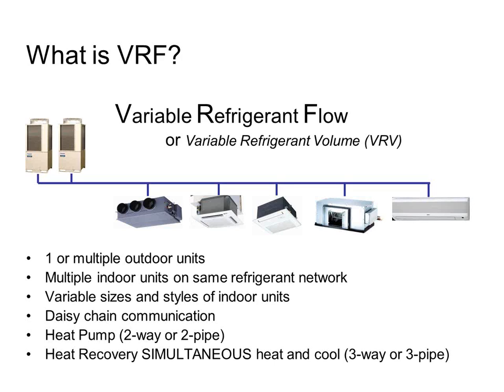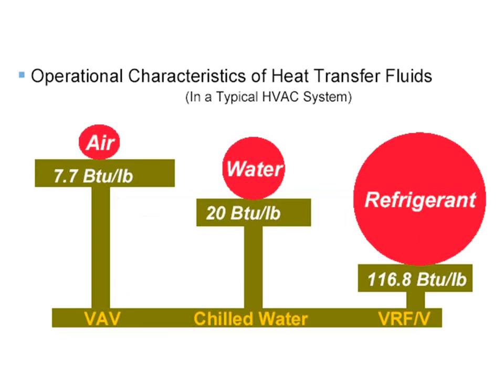Some manufacturers call that 2-way or 2-pipe because we use 2 pipes. The other type is heat recovery, also referred to as 3-way or 3-pipe because we use 3 pipes. And just for a point of note, there's actually a 3rd and a 4th pipe in both those scenarios for your condensate line, but we're talking about the refrigerant pipes in this case. So here's really the main reason why these systems are becoming more popular.